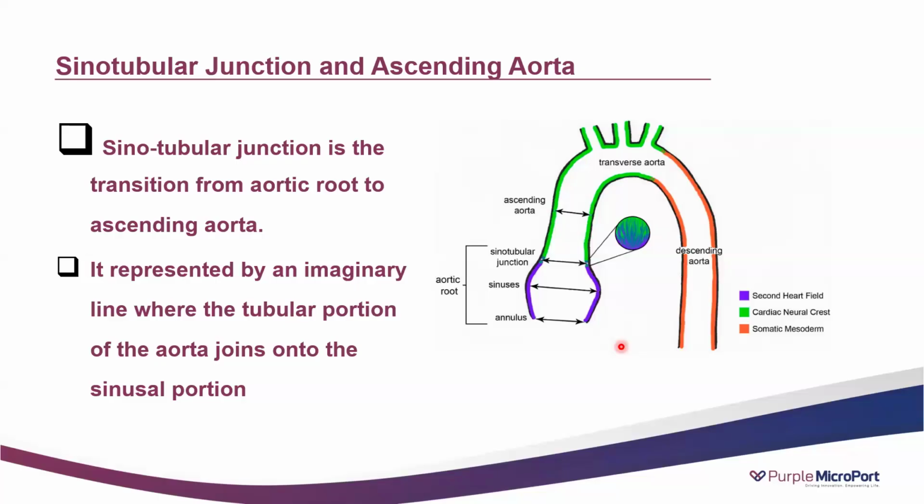Okay, so that's the significance of considering the size of these sinuses. Yes. Based on the sinuses, you may have to decrease or increase your valve size. That is a separate subject we will discuss when we do case selection. I always had confusion about why the size of sinuses is so important; annulus we can understand.